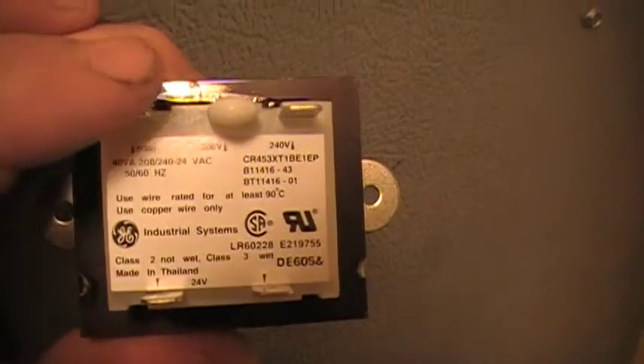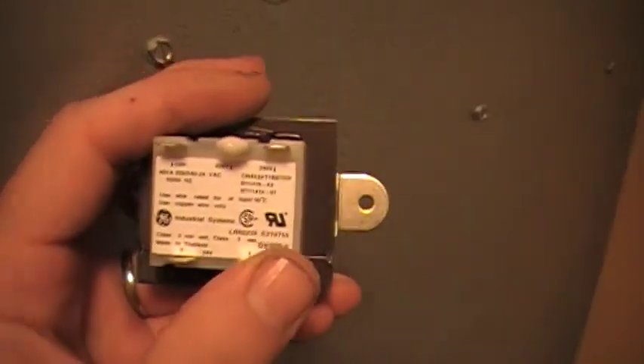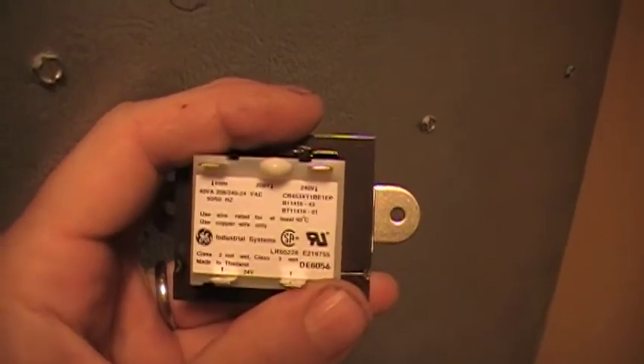here's a transformer right here. I've got a replacement. I try to buy a few spare parts because you never know when you're going to need one, and if it's on a weekend it's hard to get somebody to open up to sell you one. But what this is right here, you see on top, it's got this terminal and then the other one over here. That's where you're going to connect your 240 volts AC. And down here at the bottom, it's going to give you 24 volts AC from here to here. There's two separate windings inside this. They're completely isolated from each other. It's an induced voltage from one side to the other.